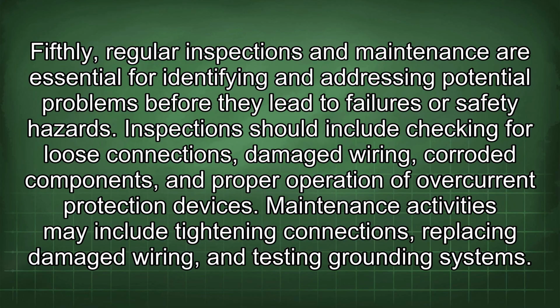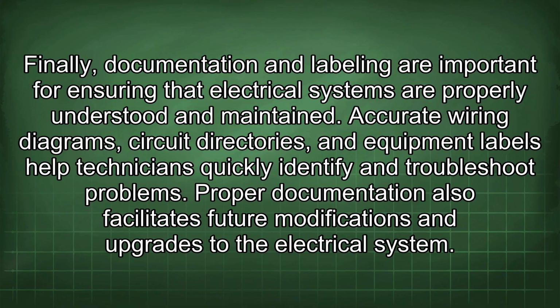Inspection should include checking for loose connections, damaged wiring, corroded components, and proper operation of overcurrent protection devices. Maintenance activities may include tightening connections, replacing damaged wiring, and testing grounding systems. Finally, documentation and labeling are important for ensuring that electrical systems are properly understood and maintained. Accurate wiring diagrams, circuit directories, and equipment labels help technicians quickly identify and troubleshoot problems. Proper documentation also facilitates future modifications and upgrades to the electrical system.